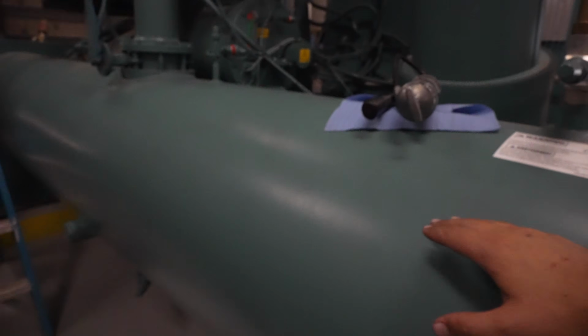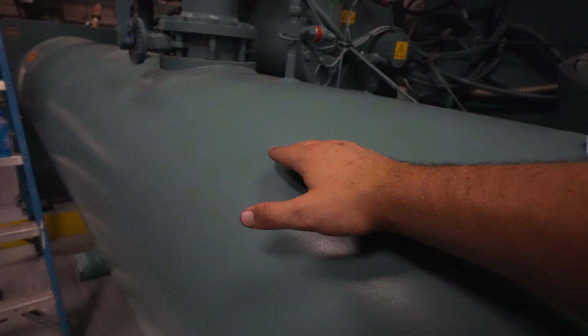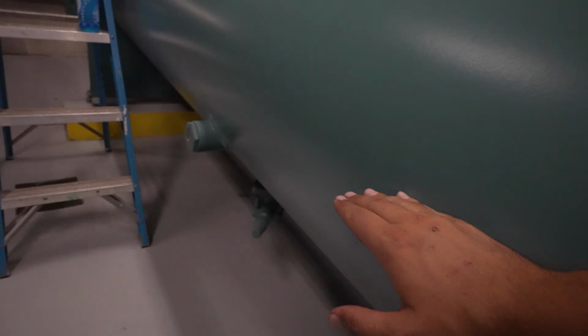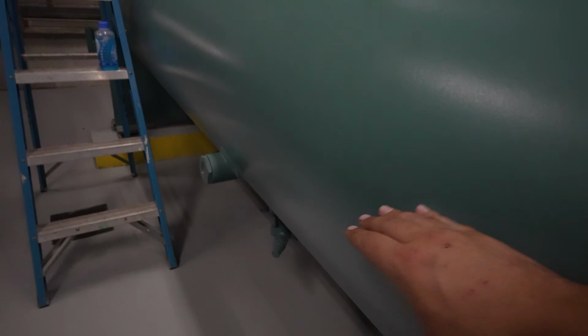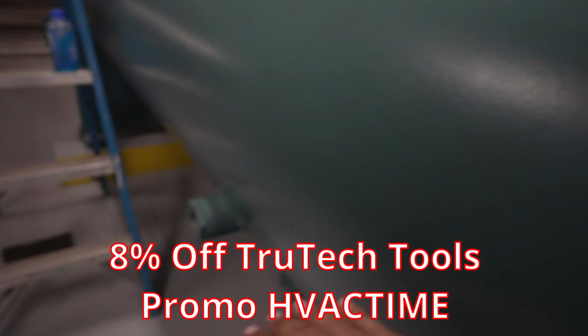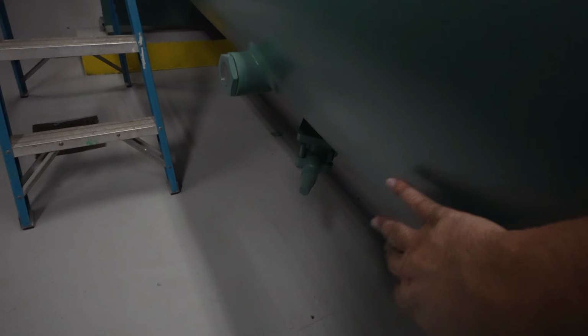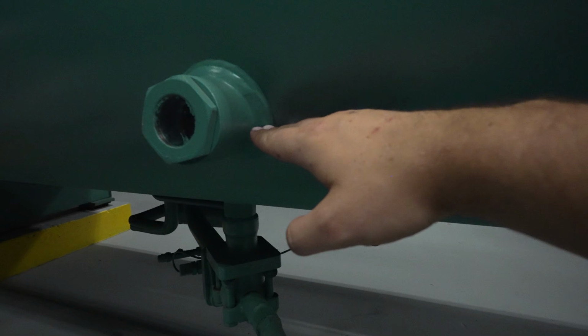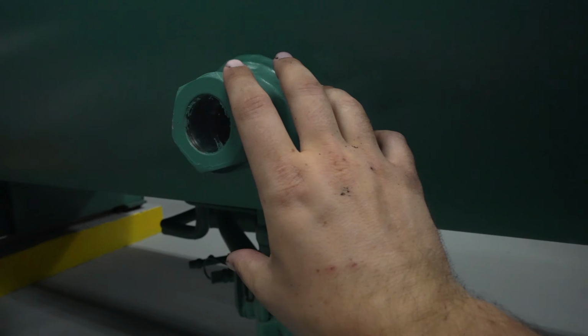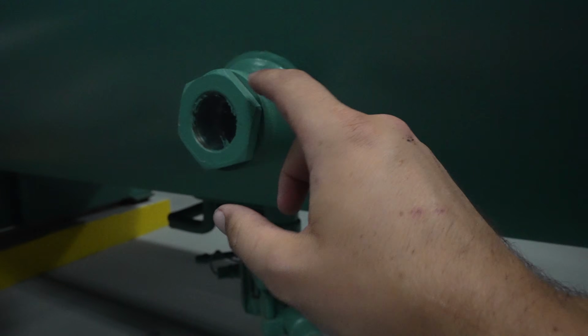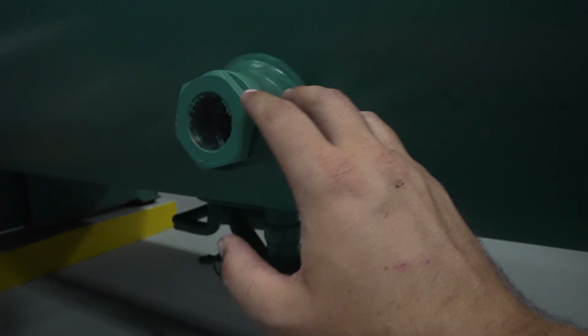On this machine, from about up here towards the top down to about halfway or so is your desuperheating tubes. This is where the bulk of the heat gets rejected. By the time it comes off of those tubes, we are down at saturation temperatures, falling into the bottom as a liquid refrigerant where we go through the subcooler. The subcooler portion is from the bottom and comes up about right here, which you can see here at the sight glass. These sight glasses are not machined perfectly by the factory, and that's part of what they tell you. And I'll explain how you're supposed to check this in a minute.